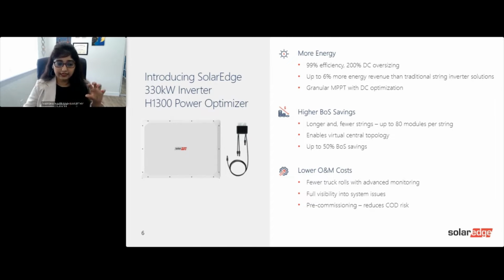And because of the centralized inverter design and the granular monitoring data that it comes with, the system offers up to 100% plant visibility, which means reduced truck rolls and increased system uptime. And not to forget that it does come with the innovative pre-commissioning feature that streamlines all the component validation prior to AC commissioning, effectively reducing any potential delays that could happen in achieving the commercial operation date. And lastly, because we are definitely the safety leader, I would say that the solution comes with the standard built-in safe DC technology that brings the voltage down to safe levels in the event of an emergency or a grid shutdown.